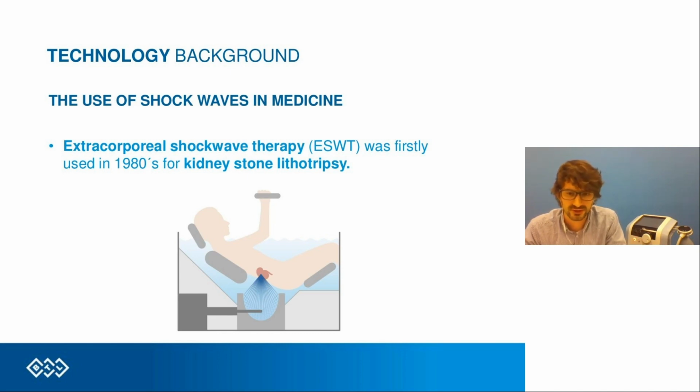As you can see in this picture, back in the day the patients were submerged into, let's say, a bathtub, and the shockwaves were passed through this water into the patient's body without any surgery, without any intervention, and without any damage to the patient's skin. So it was, and still is, a non-invasive procedure. With newer lithotripsy devices, it's no longer necessary to put the patient into the bathtub; it's possible to use these applicators and ultrasound gel instead.